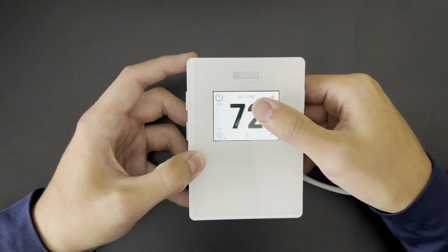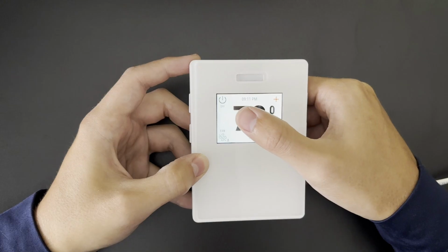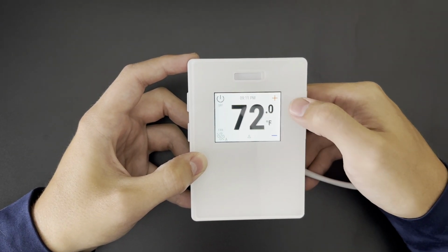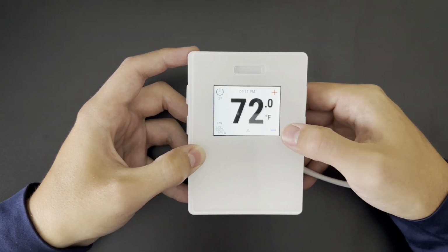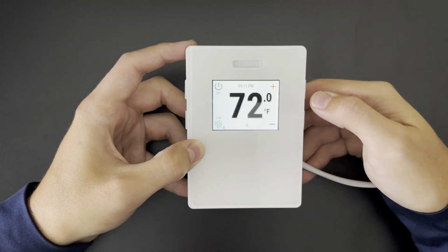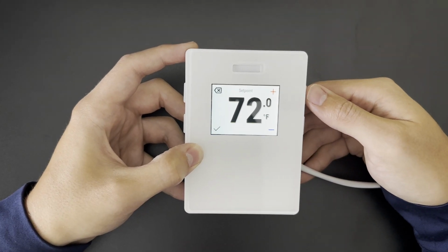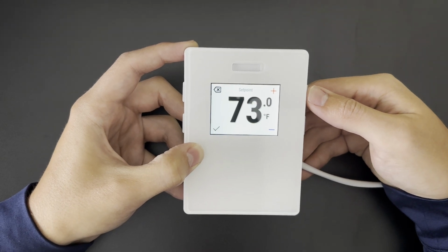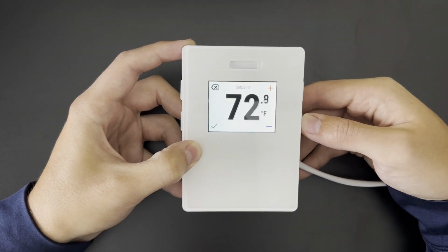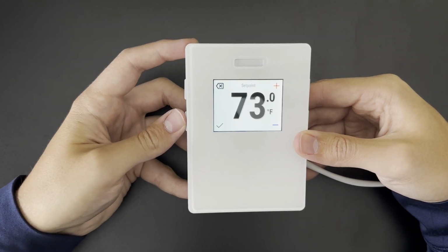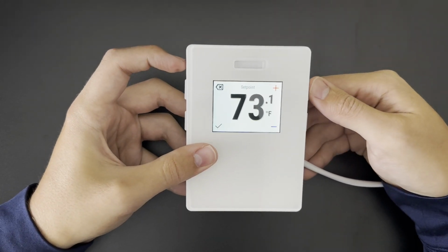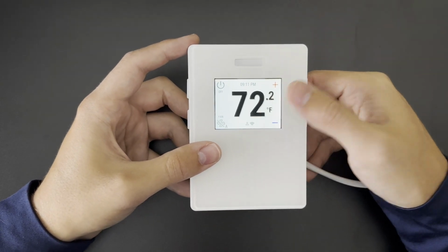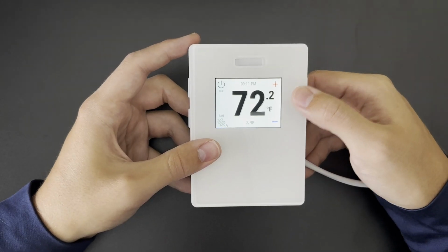I'll be greeted with a temperature here, time up here, my mode on the top left, bottom left is my fan, and then I've got set point adjust here for raising the set point or lowering the set point. So if I want to raise or lower the set point, I click one of the two set point adjust buttons, and then I can adjust in 0.1 degree increments up or down. And then if I want to save that, I'll hit the check. If I don't want to save my changes, I'll hit the top left button, which is the X, and it'll take me back to the main screen here.